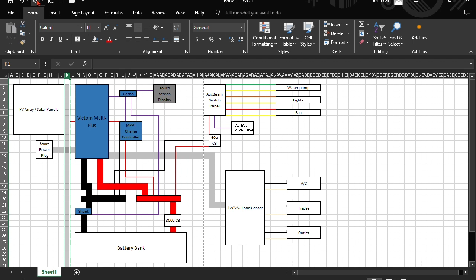So now we've got kind of a quasi-complete system where our sun comes into our PV array, goes through the circuit breaker all the way over to the MPPT charge controller, then drops down to the battery bus bars and charges the battery. Then the multi-plus produces 120 volts, which comes out and goes over to the 120 volt load center, running your refrigerator, your AC, your outlet, whatever else you've got wired into it. And also our 12 volt comes off of our bus bars up to our aux beam switch panel, which has the control here, and runs our water pump, our lights, and our fan.